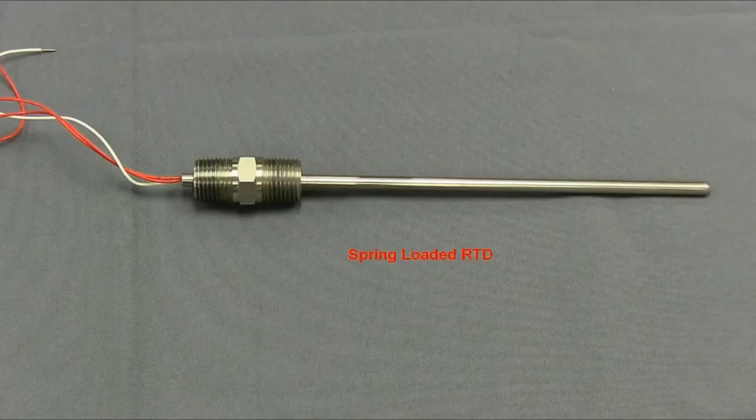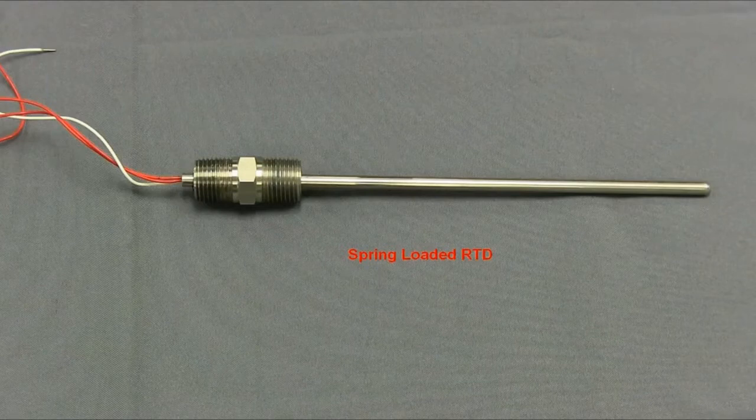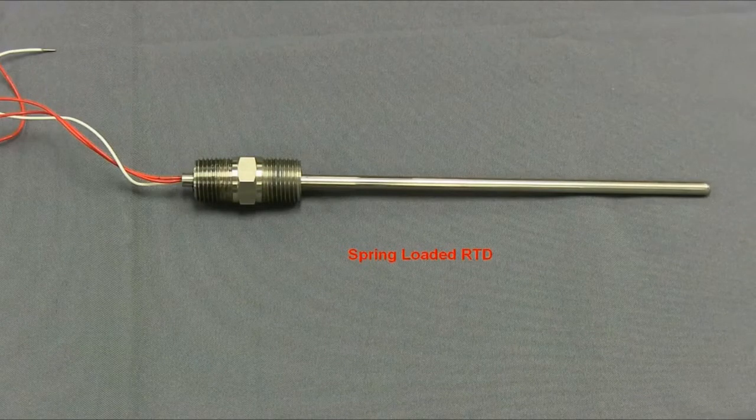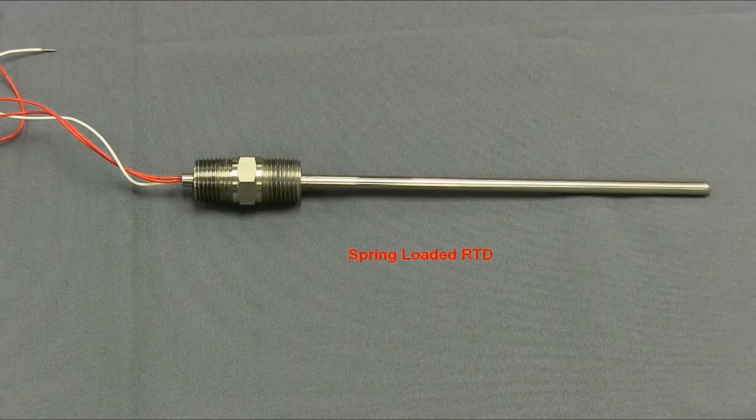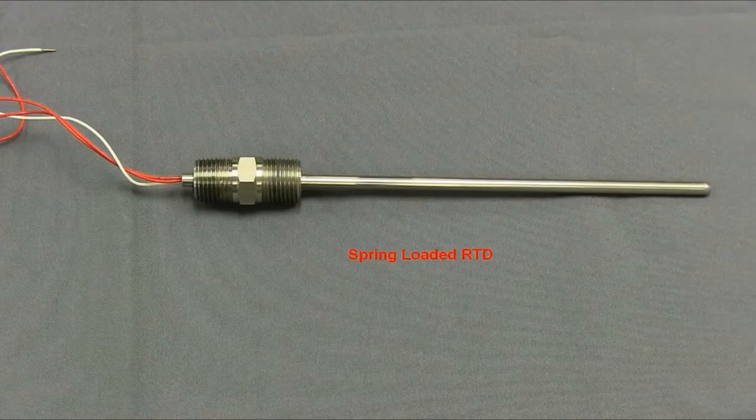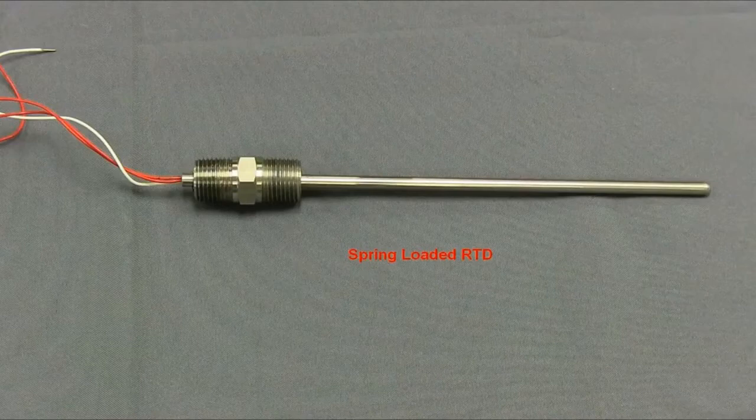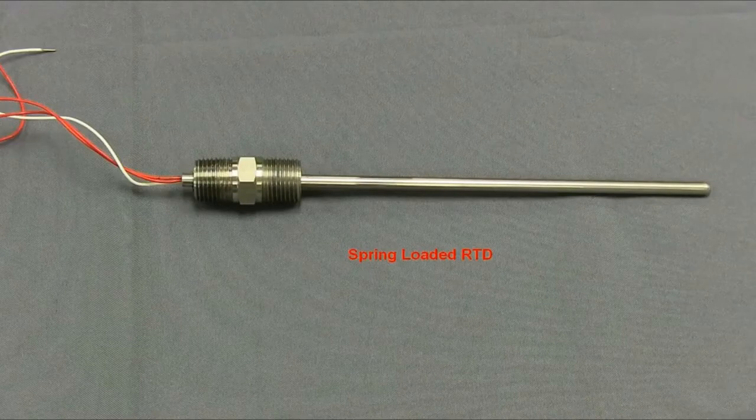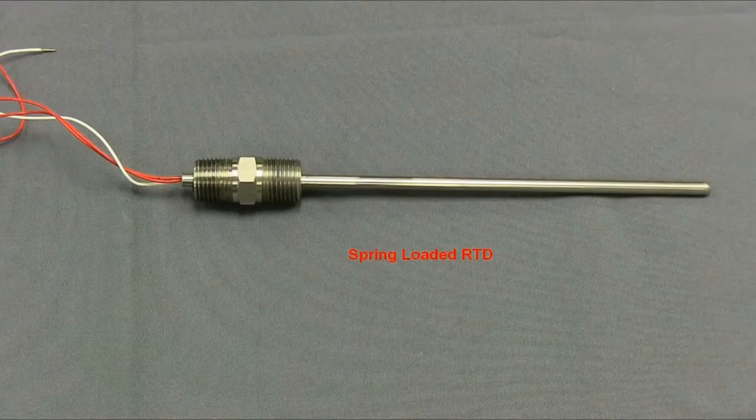The sensors used with the thermowell mounted transmitter are always spring loaded. This ensures the sensor is always in contact with the bottom of the thermowell. This is necessary because the sensor takes the measurement at the very tip. A sensor not making contact with the bottom of the thermowell will create incorrect readings.